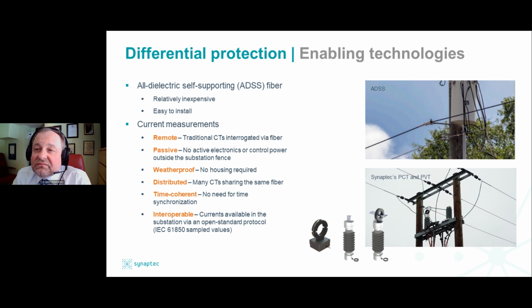I would like to have remote measurements, meaning traditional CTs are interrogated via fiber. Interrogated meaning accessed. The system needs to be passive, meaning no active electronics or control power outside of the substation fence. Weatherproof, I don't want to be building any housing for that equipment. Distributed, meaning that I could access many sites through the same fiber. Time coherent, so all the current signals are aligned and I don't need any time synchronization solution either outside of the substation fence or inside. And finally, interoperable, meaning that when those signals are given to me in a substation, I want them in a format that could be understood by many other devices. So practically, we are talking about IEC 61850 sampled values.